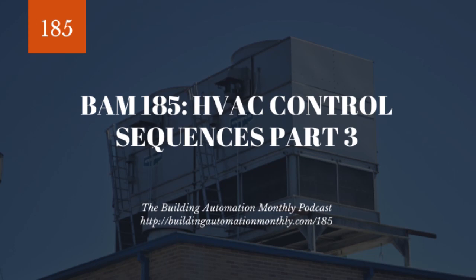Because if you don't have ventilation, if you don't have airflow, then you're not going to satisfy ASHRAE 62.1. The space air is going to get stagnant. People are going to start to get tired. You can actually get people quite sick if you aren't removing CO2 and things like that, depending on your building envelope and how well sealed it is and how well your pressurization strategy goes. You can essentially fill a space with really bad air. Because remember, at the end of the day, air, just like water, has mass and volume and will fill a space. Air is actually an object, and a lot of folks don't realize this.